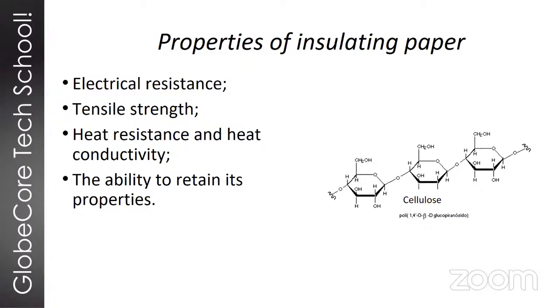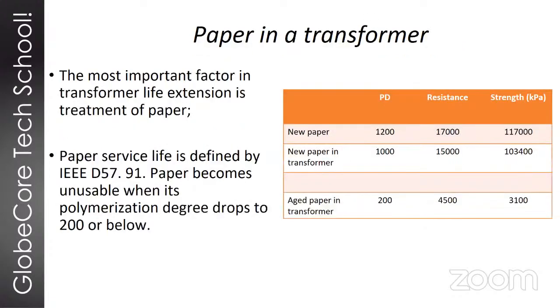So let's go to the next slide. To estimate the condition of paper insulation, there is a number that is used. It's called the degree of polymerization, or polymerization degree. In this slide, there is a table that gives you a connection between polymerization and the mechanical strength of paper. And we can see that new paper can withstand a load of up to 117,000 kPa. If the paper is aged, basically it only can withstand about 3,100 kPa. So new paper usually has a polymerization degree of 1,200 or 1,250 or so.